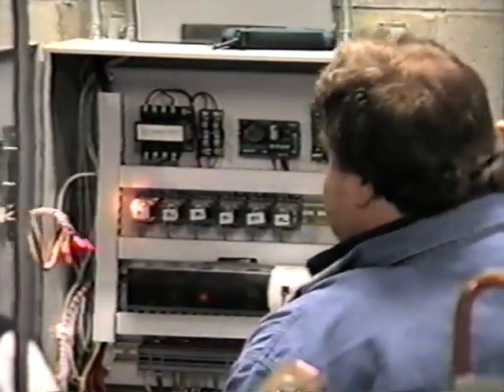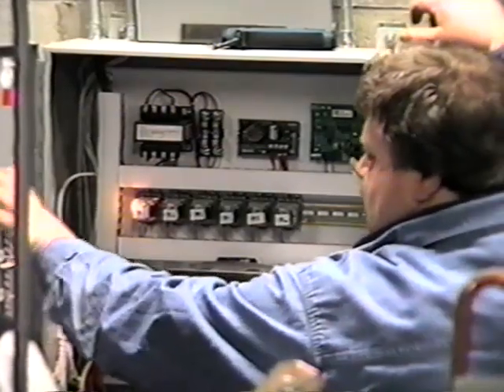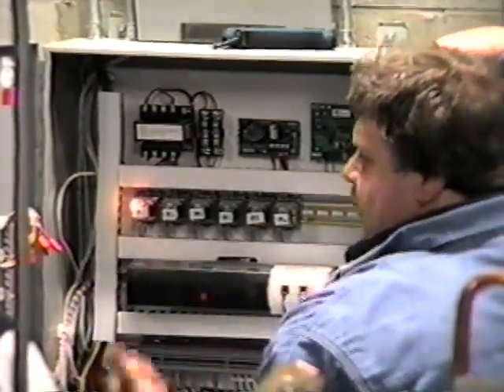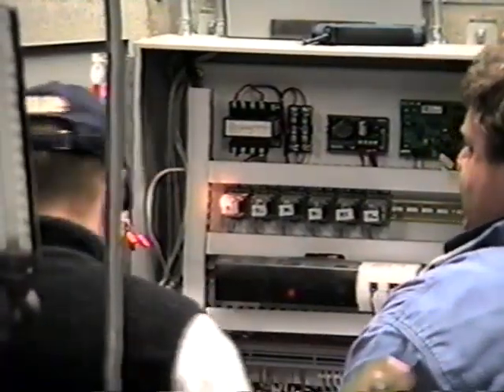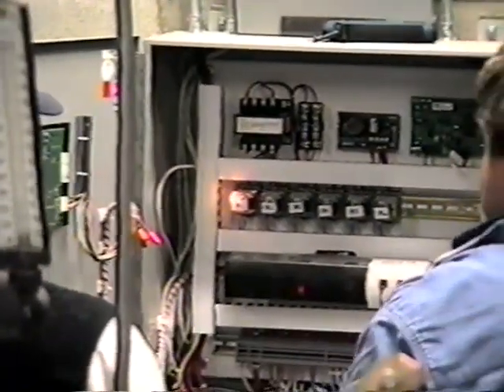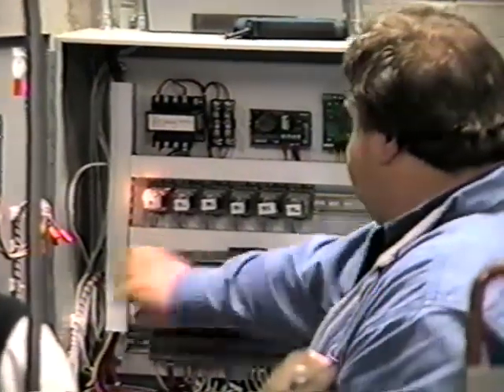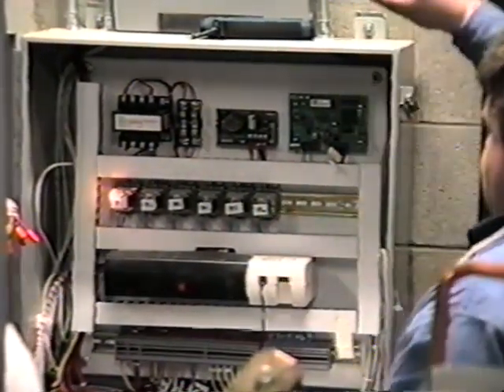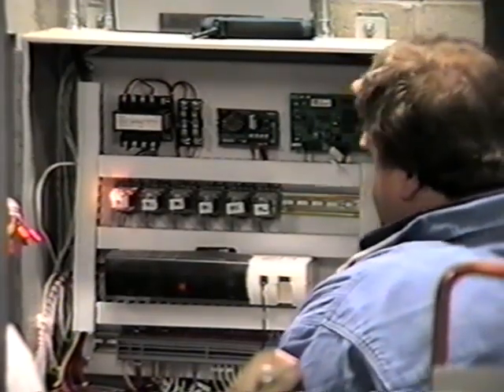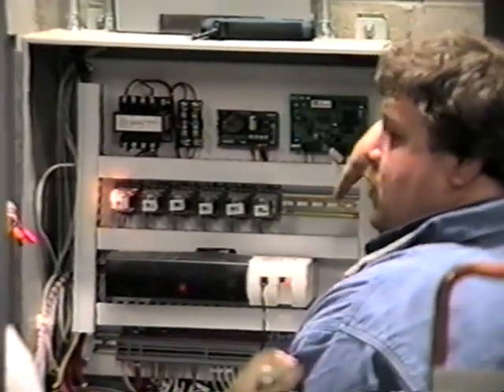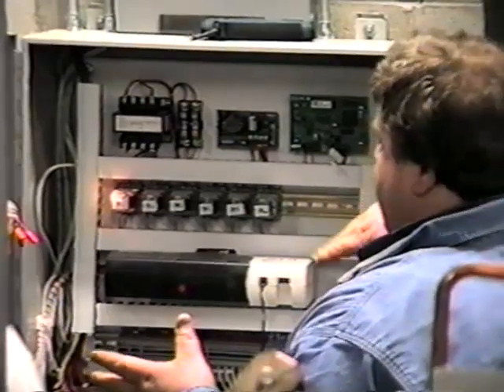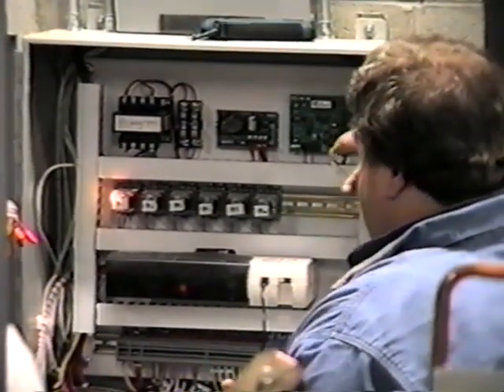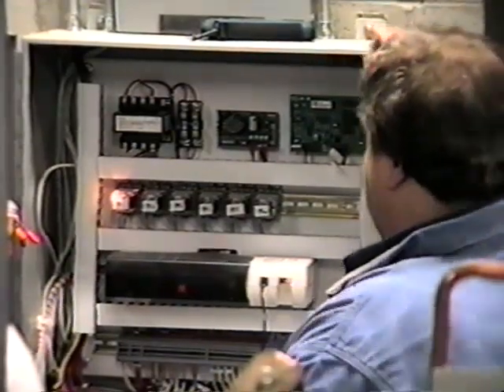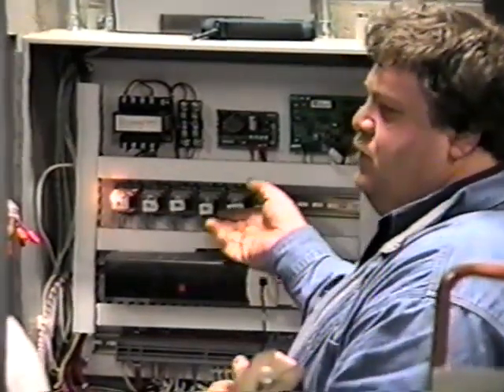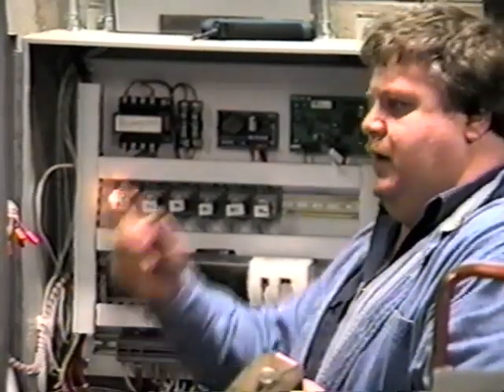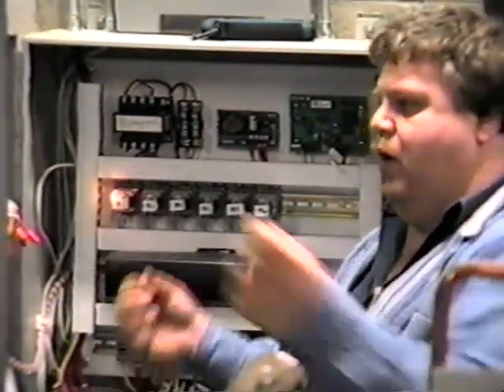Then just so you know what we've got inside, this display, as he had with the navigator there, is your human interface. It's how you talk to the rest of the system. And basically that's just this one controller. It has a pretty sophisticated brain in it, and we've custom programmed this to do the function we want for the ice rink. Anything that's an output, for the most part, we put a relay in to do that function. So we pulled wires from the underfloor heat pump, the chiller, or whatever.